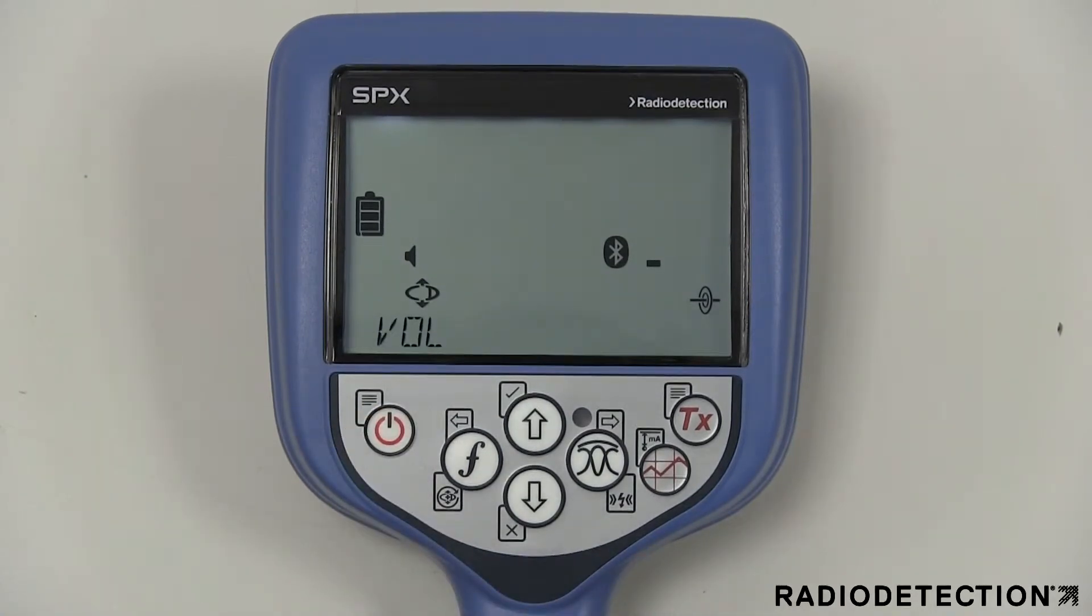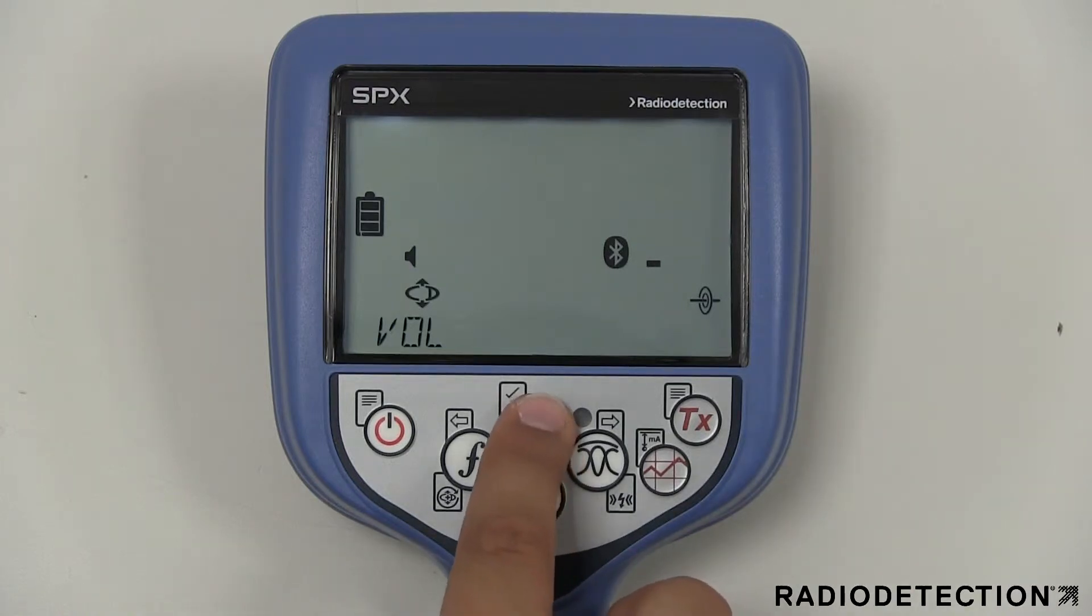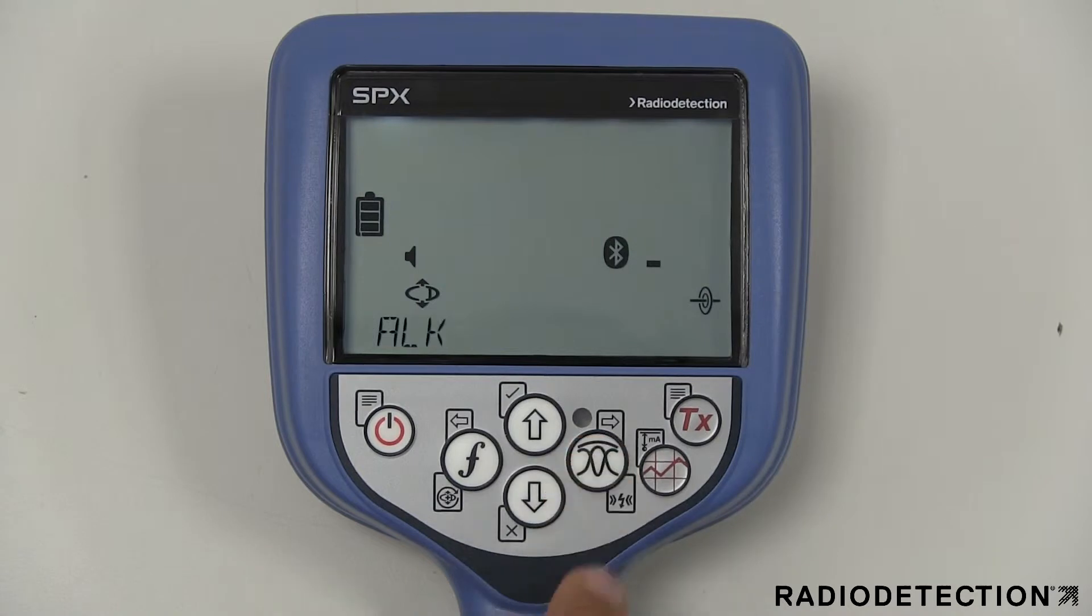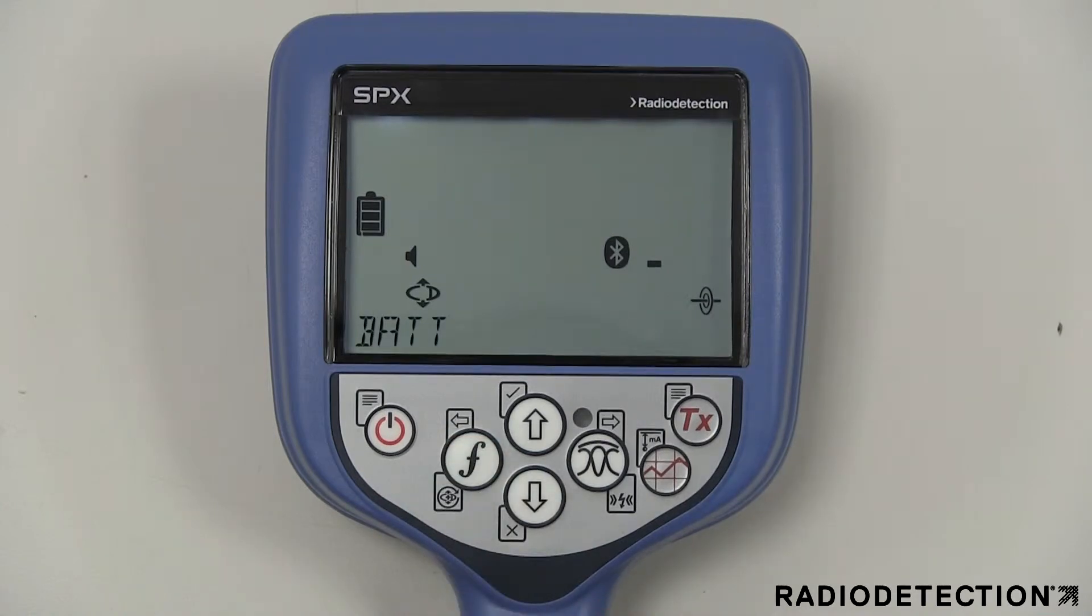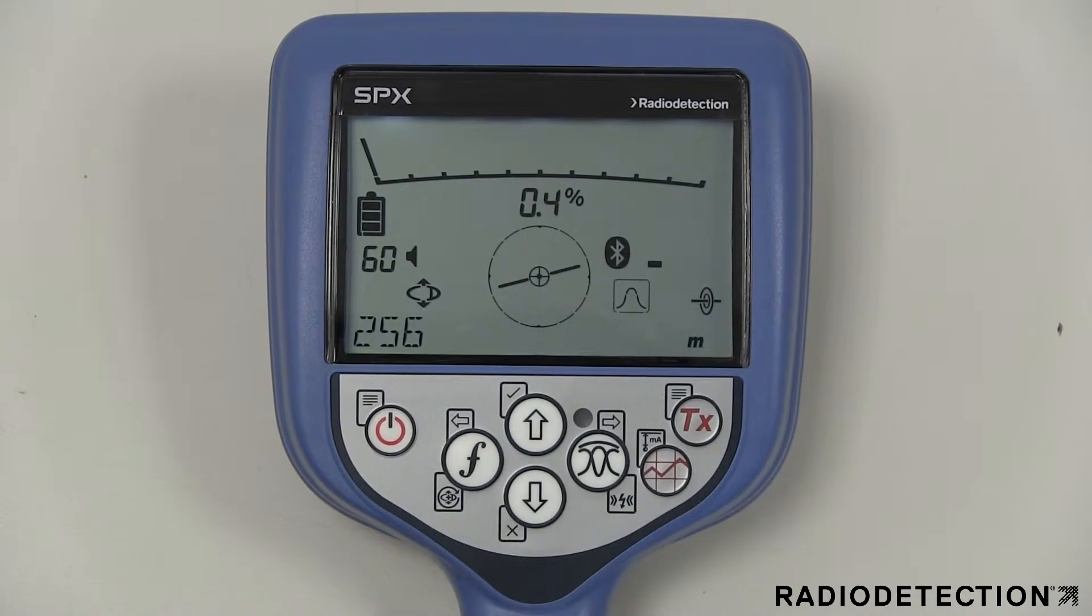To navigate the locator menu, press the power key briefly to enter the menu, use the up and down keys to scroll through the menu options, press the antenna key to enter the option submenu, use the up and down arrows to scroll through the submenu options, press the F key to make a selection and return to the previous menu, then press the power key again briefly to return to the main operation screen.